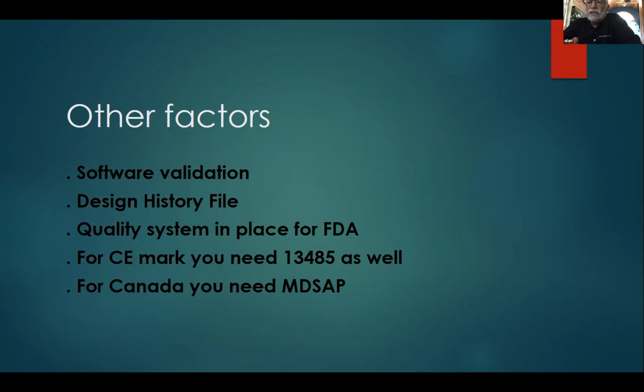Is the quality system in place for the FDA? As I explained, for a PMA, you're going to have a pre-award inspection, and the FDA is going to come out and make sure your quality system is in place. For 510K or de novo, they'll do that inspection after you start marketing your device.